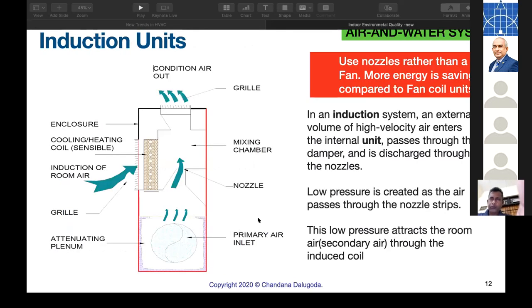Now, this is a typical induction unit. This is what you can see, a cross-section of the induction unit. You have a circular spigot here. The conditioned air duct comes from somewhere down and connects here. Now, don't think this air duct is as big as in normal air conditioning, but it is quite small because we are supplying only ventilation air, with dehumidified air over and above what is required to absorb water vapor. Now, mind you, this air is pressurized.